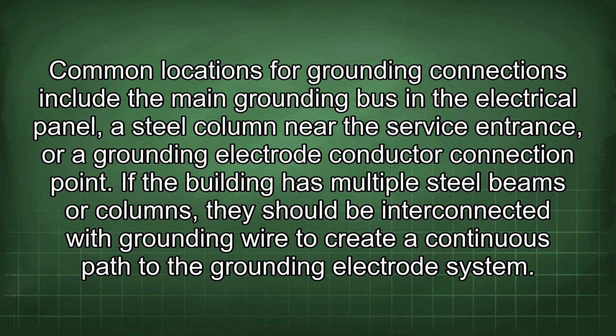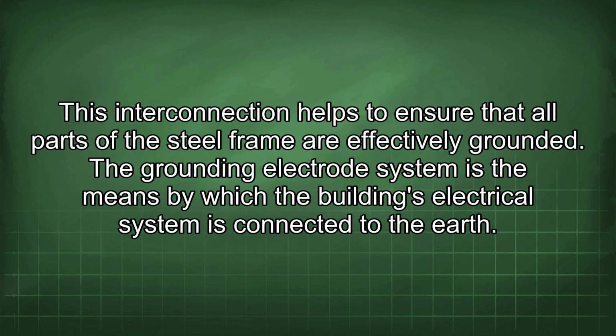If the building has multiple steel beams or columns, they should be interconnected with grounding wire to create a continuous path to the grounding electrode system. This interconnection helps to ensure that all parts of the steel frame are effectively grounded. The grounding electrode system is the means by which the building's electrical system is connected to the earth.